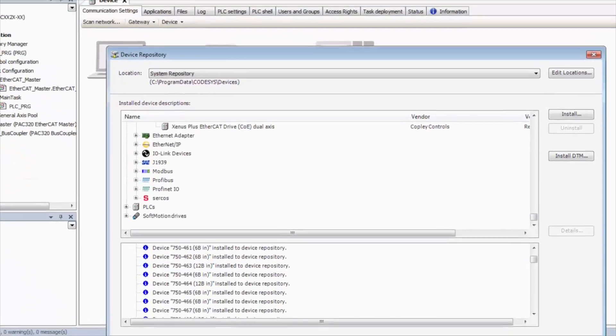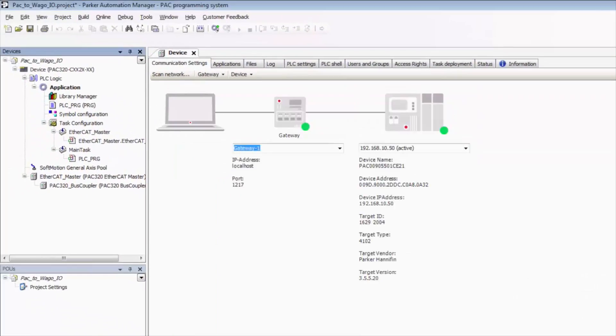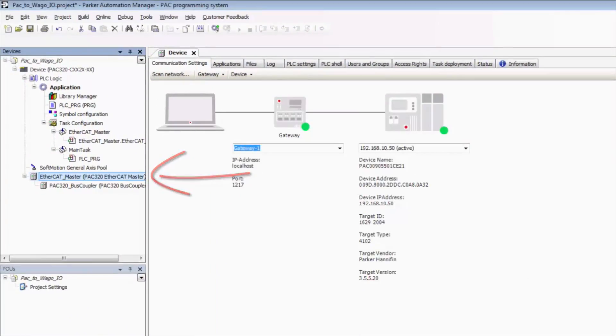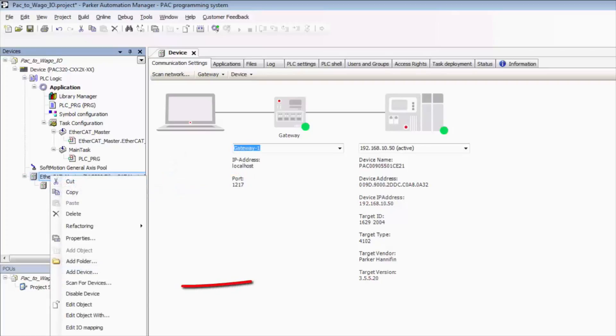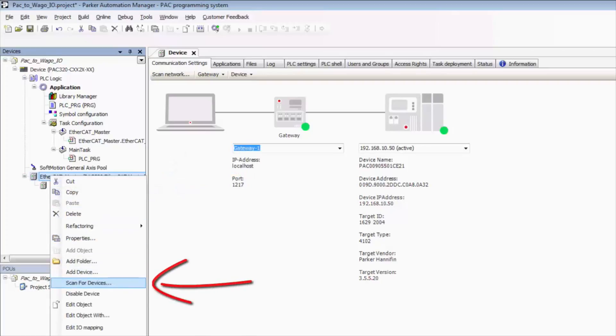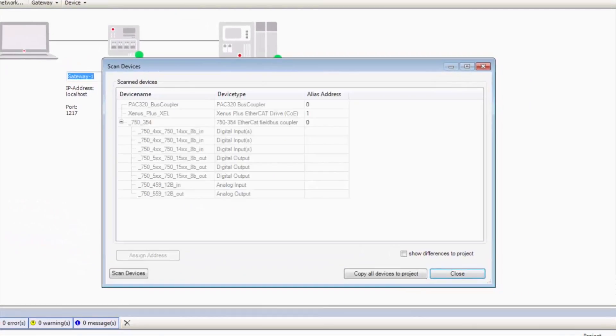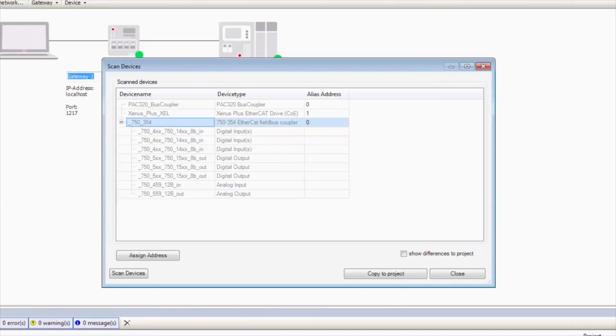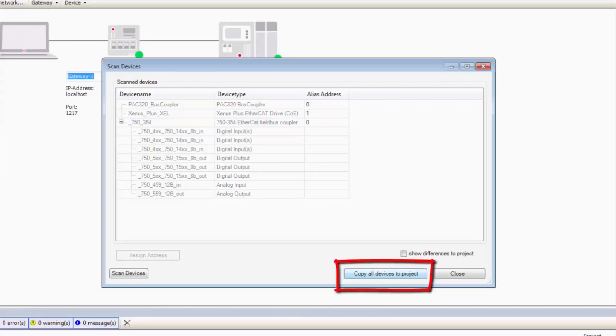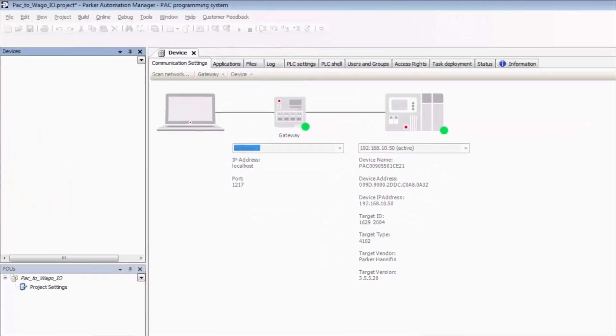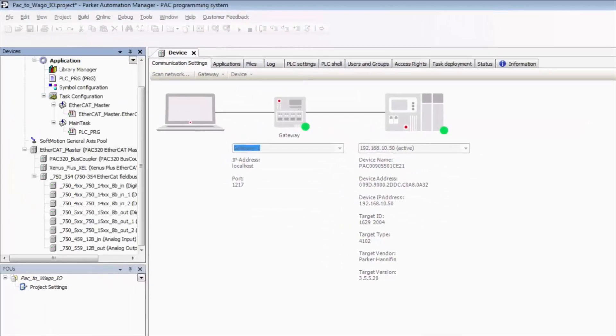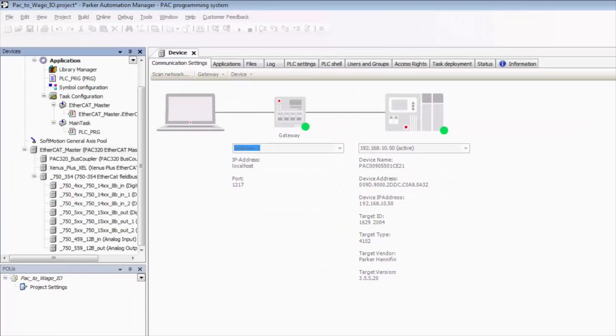So now that that's completed successfully, we can close that, click EtherCAT master again, right click, go to scan for devices, and now we see that we've found our WAGO EtherCAT IO coupler. So now all we need to do is unselect that, click copy all devices to project, and it's going to add our drive and our IO to our project tree.